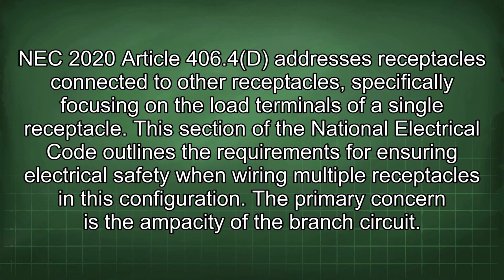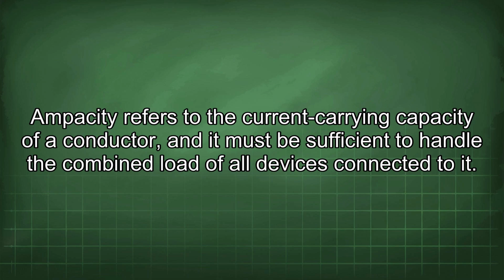NEC 2020 Article 406.4d addresses receptacles connected to other receptacles, specifically focusing on the load terminals of a single receptacle. This section of the National Electrical Code outlines the requirements for ensuring electrical safety when wiring multiple receptacles in this configuration. The primary concern is the ampacity of the branch circuit. Ampacity refers to the current carrying capacity of a conductor, and it must be sufficient to handle the combined load of all devices connected to it.